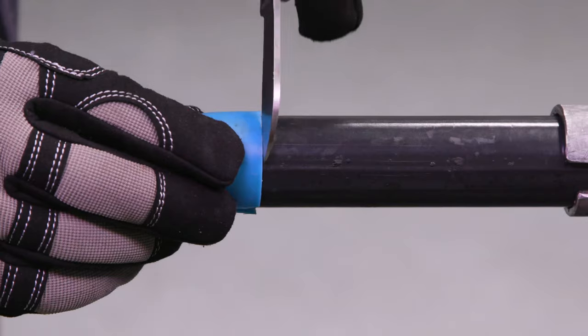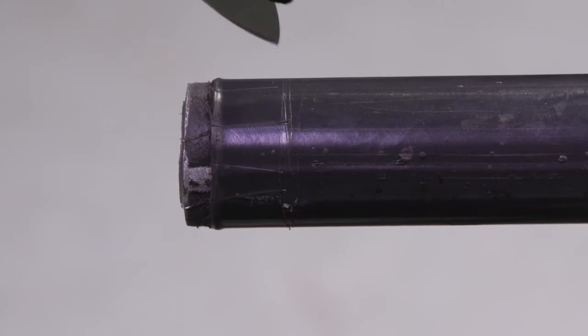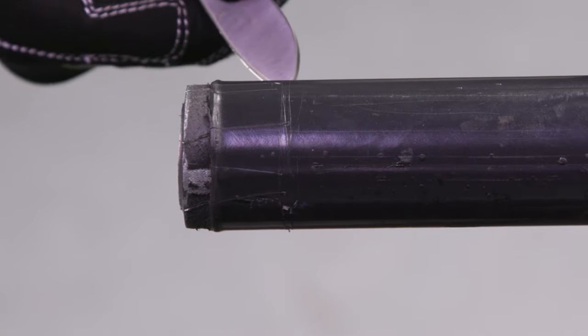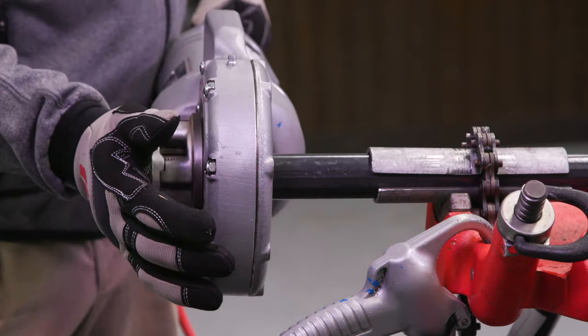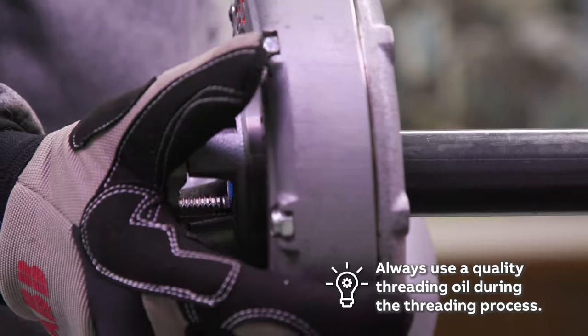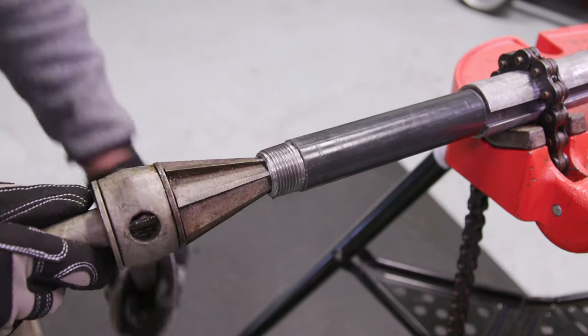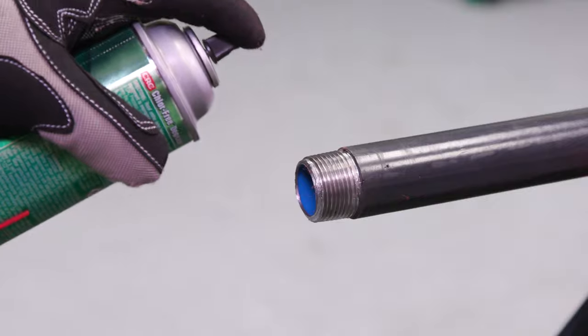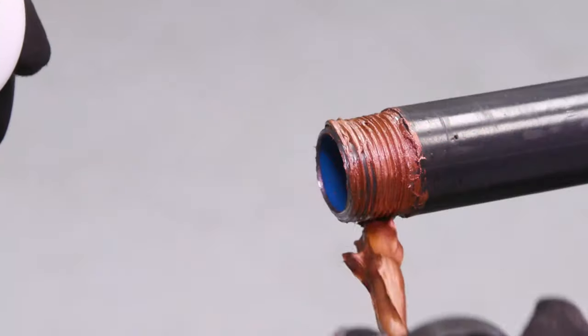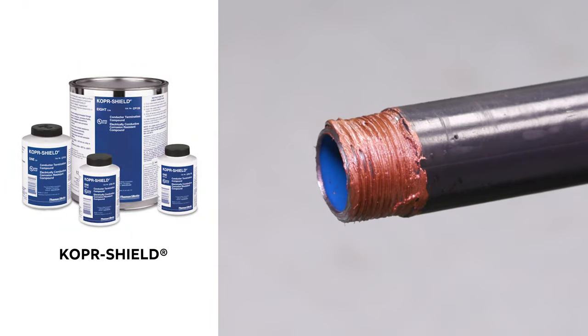First, use a conduit thread cap to determine the proper length you need to score from the conduit end. Next, use a knife and score the conduit lengthwise from the point where the threads will end to where they begin. Now it's time to thread the conduit. Due to the lengthwise scores, the PVC and the metal shavings are able to evacuate from the die head with the threading oil. Be sure to use a quality threading oil during this process. Once the threading is complete, ream the conduit with approved reamers. Spiral and straight style reamers are both acceptable. Next, clean the threads with a quality degreaser. Coat the threads with Thomas and Betts Kopr-Shield compound. Ocal blue urethane thread compound can also be used as a coating.